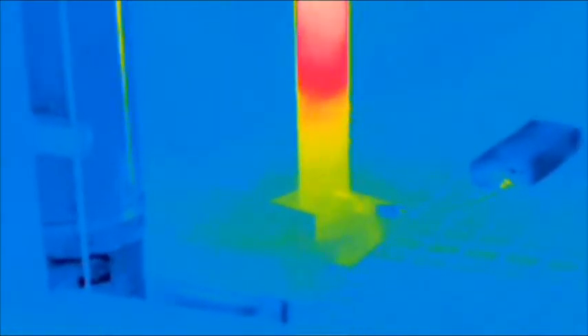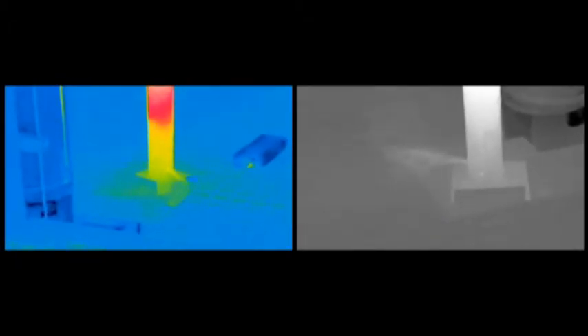Schiller has found leaks in unexpected places that would never likely have been found without an optical gas imaging camera. We found lots of gas coming into one of these junction boxes, and we were really surprised. It was a very funny place to find gas because you never expect to see gas in the insulation. Also, we had one pipe support on the bend — they had welded this pipe support a little bit too tight, so the gas was leaking from the pipe into the pipe support and out at the bottom. They tried before with the sniffer to find this leak because they could smell ethylene, but they could not find it with the sniffer.